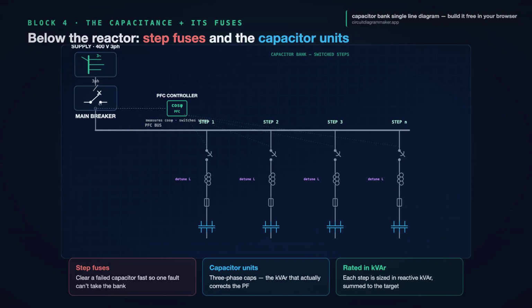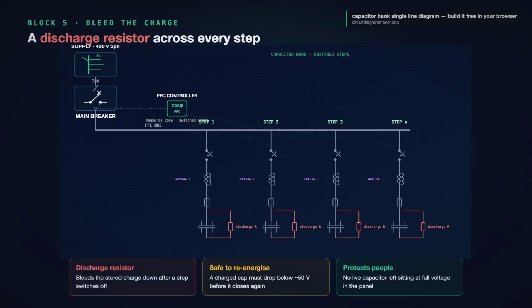And below the fuses, the capacitors. On the single line diagram, they're the classic symbol, the parallel plate marks, 3 of them for a 3-phase step. These are the kilovolt amps reactive, the kVAr, that actually correct the power factor. Each step is rated in kVAr, and the controller sums the steps it has switched in to reach your target. Fuses to protect them, capacitors to do the work.